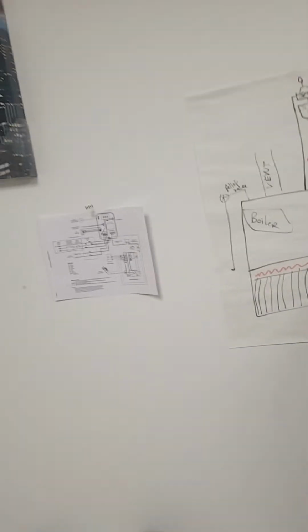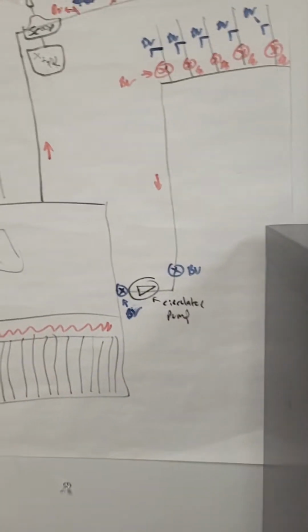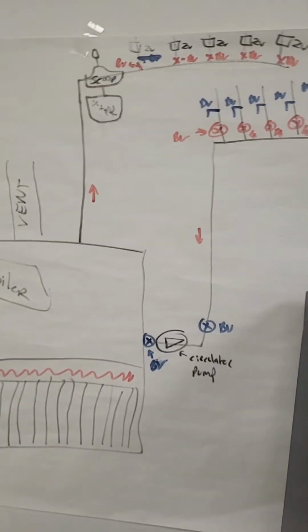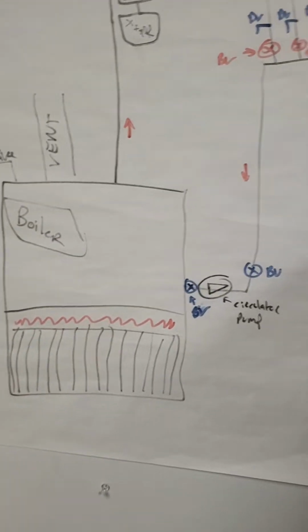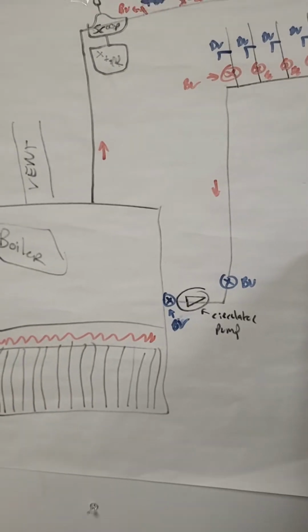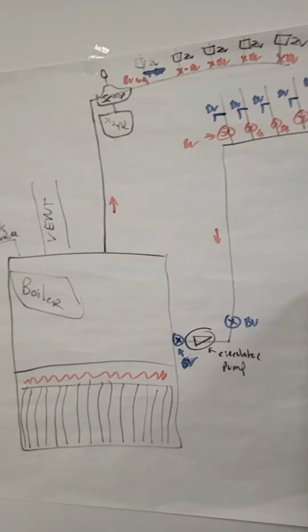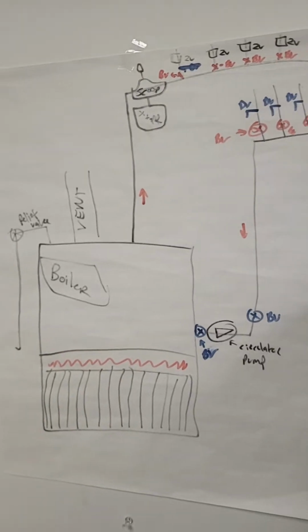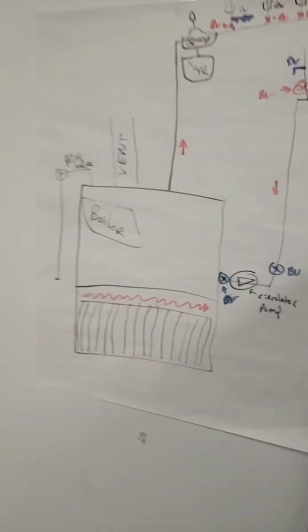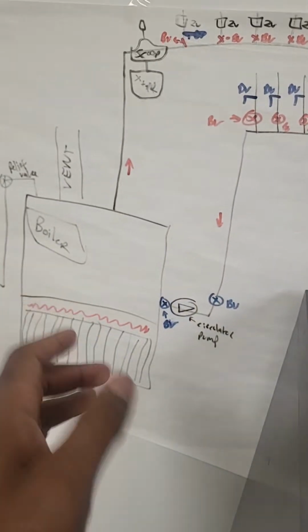But guys, I'm not here to talk about illustrations. We got to talk about low water cutoffs, guys. Now, low water cutoffs, I think this one is a Watchdog or a Bird Dog. I think it's Watchdog. Guys, they make float switches for air handlers and coils. Now, guys, here's the thing. You're not necessarily going to need a float switch on a hot water or steam boiler.